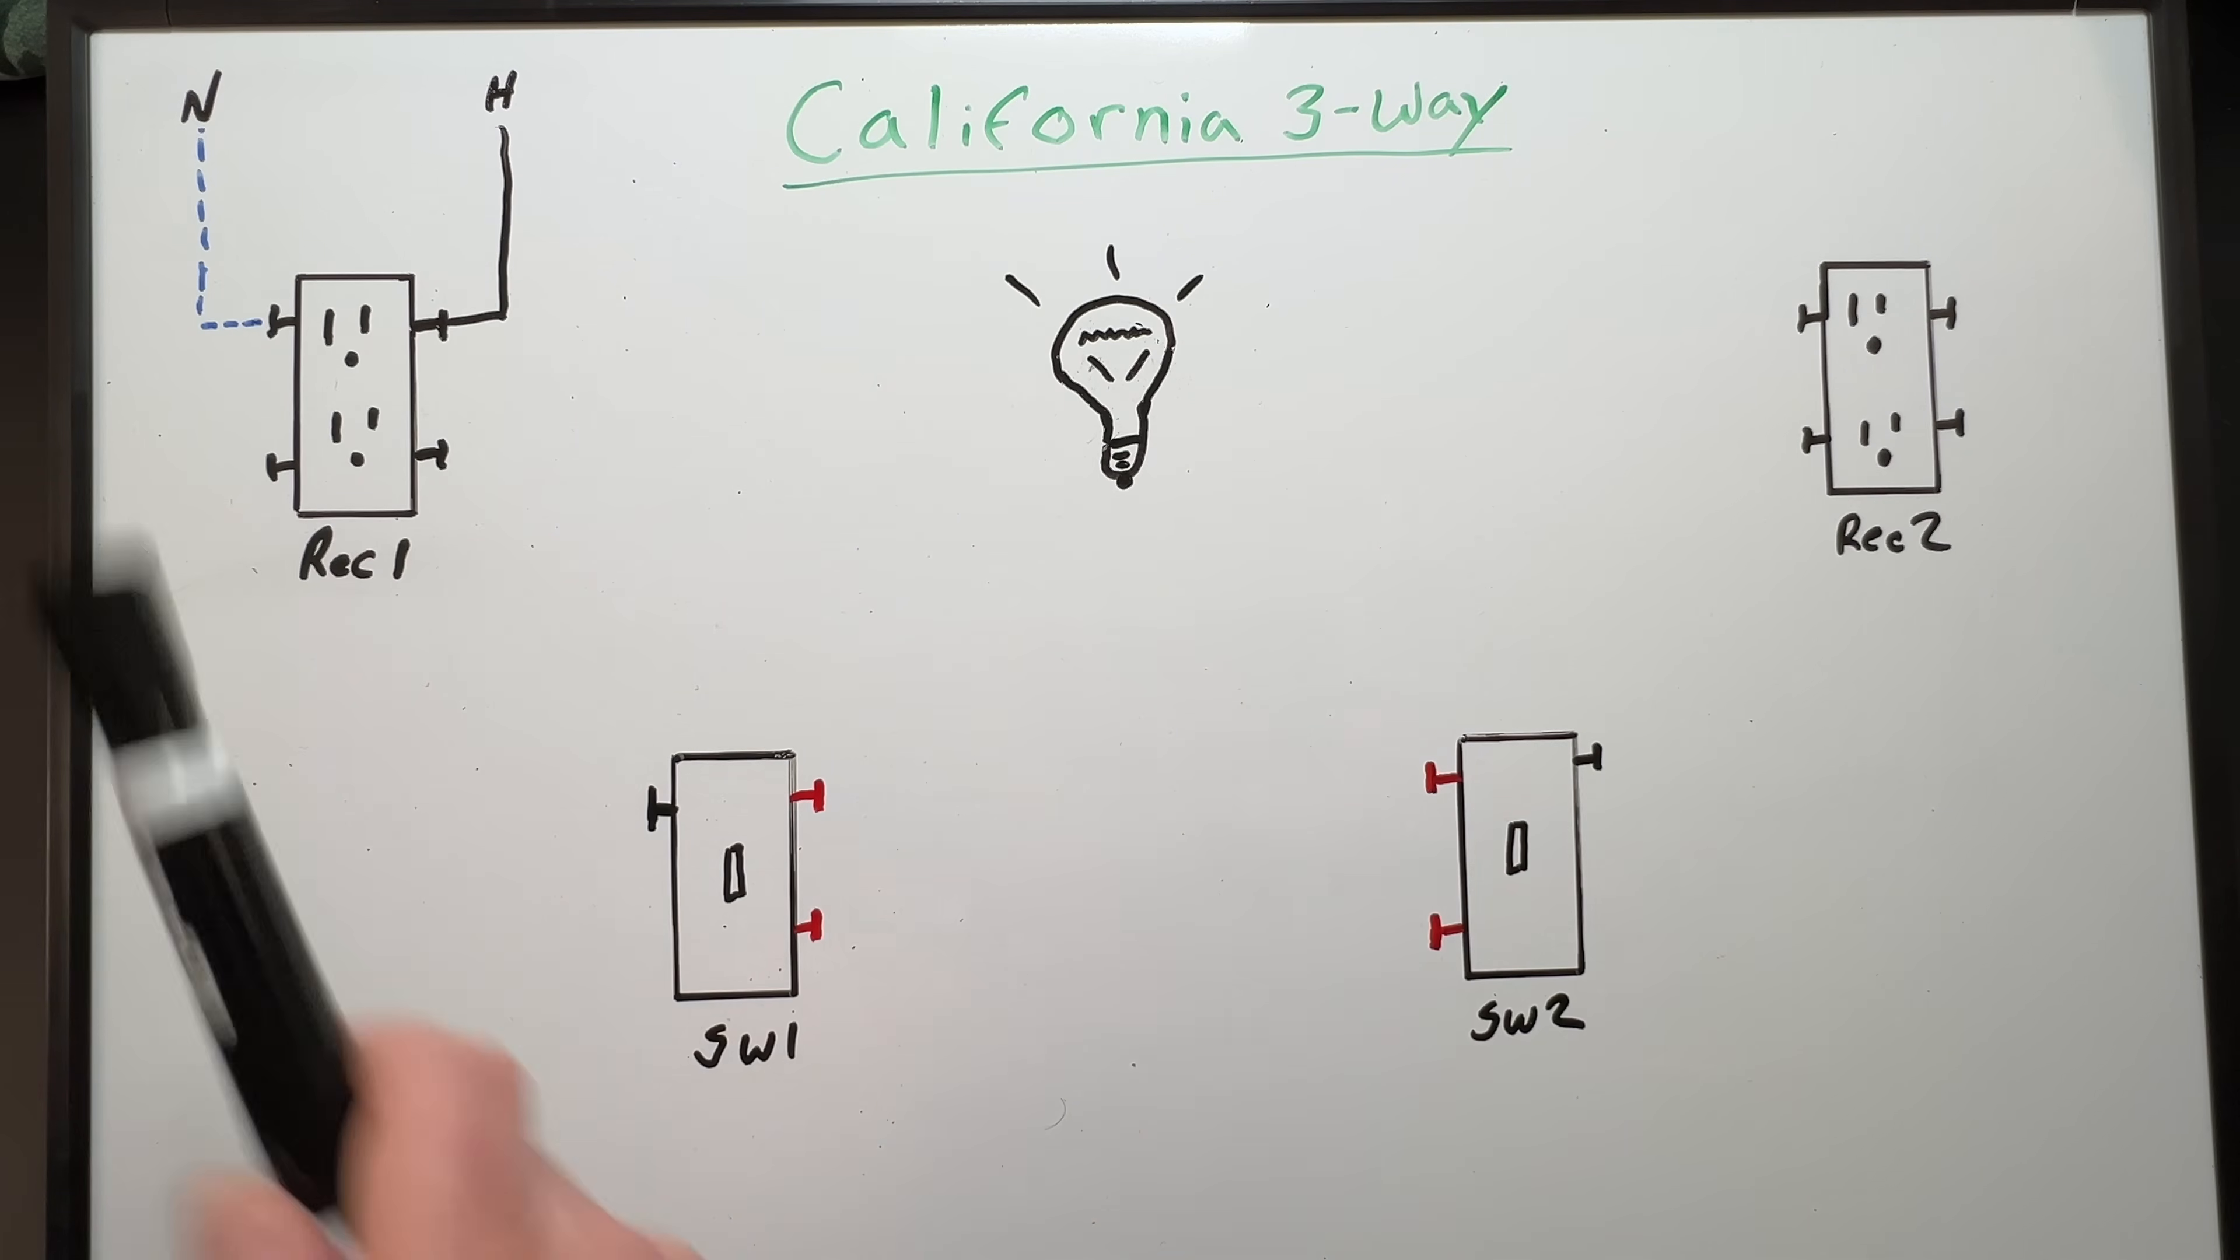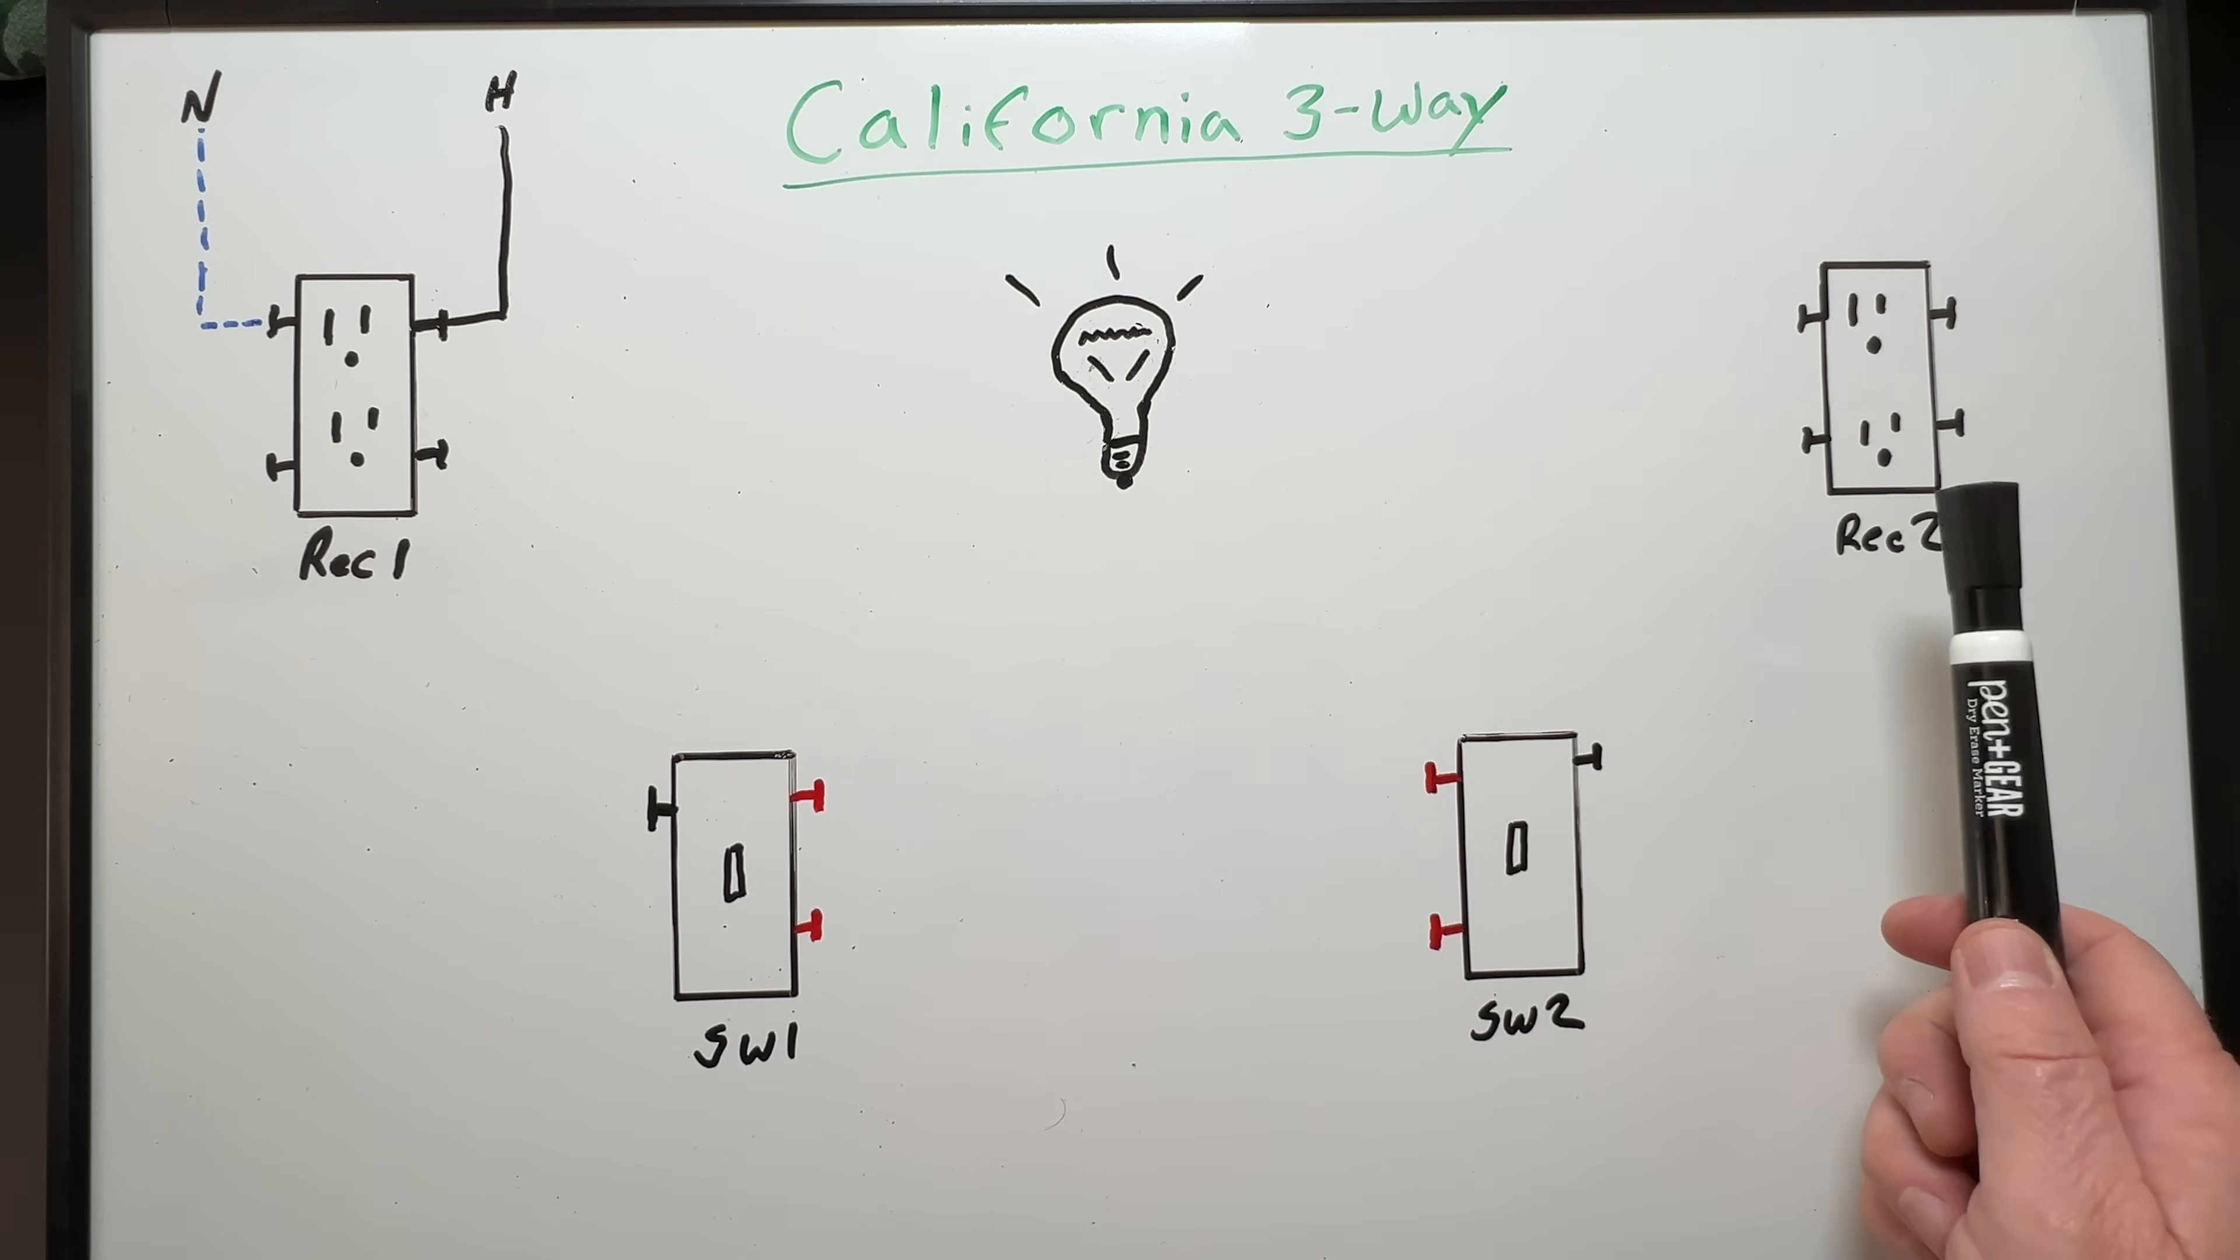We're going to carry unswitched power from receptacle one to switch one to switch two and then on to receptacle two. Our neutral will bypass the switches altogether. And then of course, each switch will control our light.